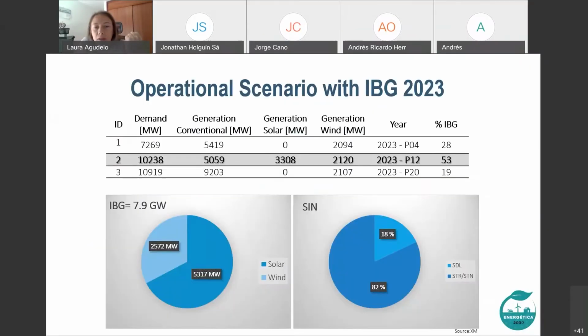Today, in our Colombian system, we have connected less than 100 megawatts of inverters in high voltage, and we expect to have almost 8 gigawatts installed in the next 3 years. For example, in this slide, you can see the inverter scenario for 2023. We have a table with the 3 main scenarios in Colombia for this year: demand, conventional generation, solar and wind generation. They are all inverter based, and for the year 23 for every period, 4 for minimum, 12 for medium, and 20 for maximum demand in the Colombian system.